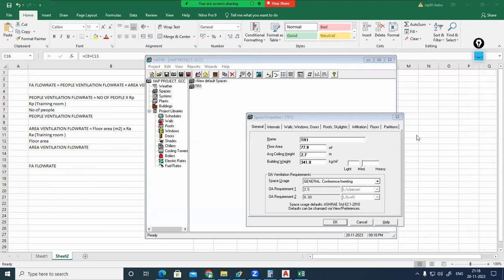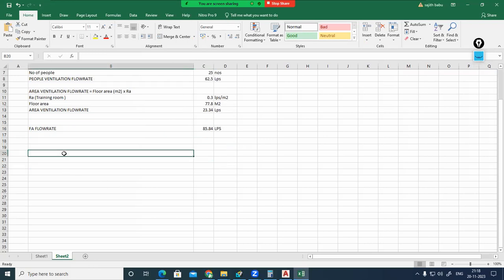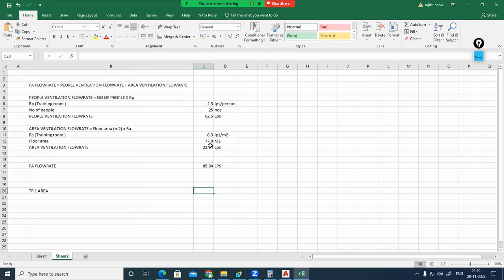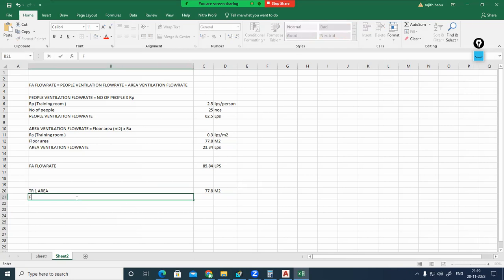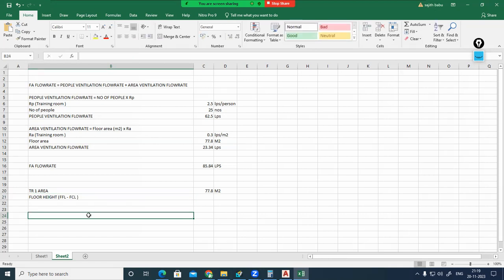Correct. By that consideration, for example, I have this training room. So, you know the training room area? Training room 1, area, how much is it? The area is 77.8 meter square, correct? 77.8 meter square. For the floor height, when you are calculating it for the ventilation calculation, consider from the finished floor level to the false ceiling, not until the bottom of the slab. But if you do not have a false ceiling, consider from the finished floor level to the bottom of the slab. If you have a false ceiling, consider the height from finished floor level to the false ceiling. If you do not have a false ceiling, then finished floor level to the bottom of the slab.